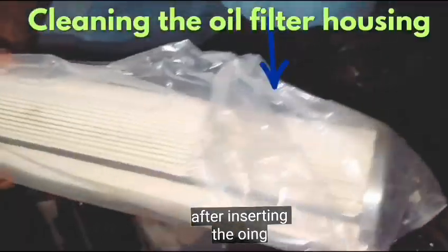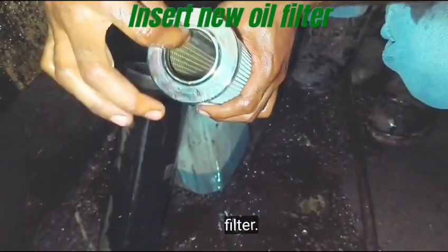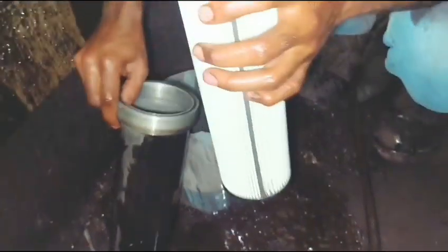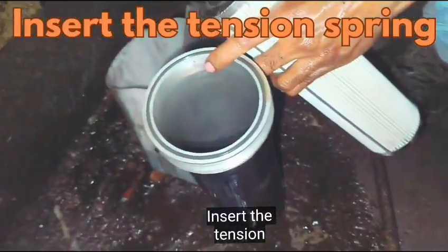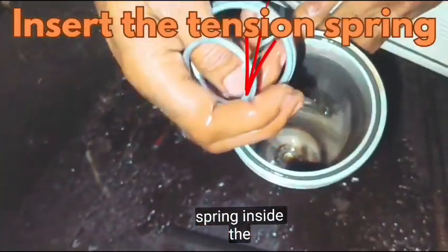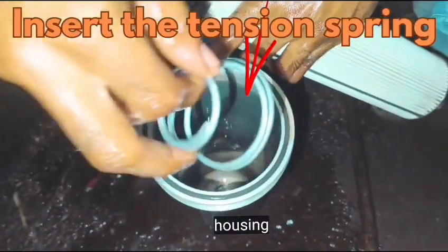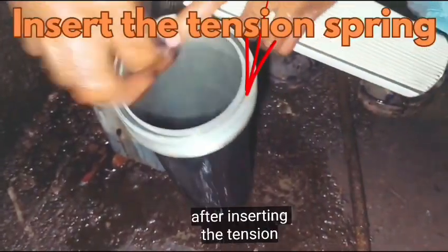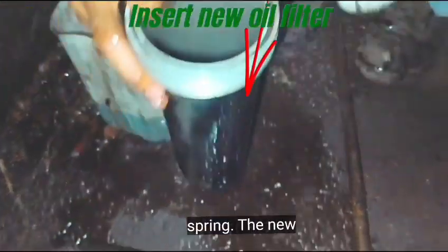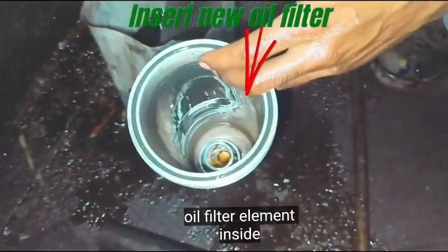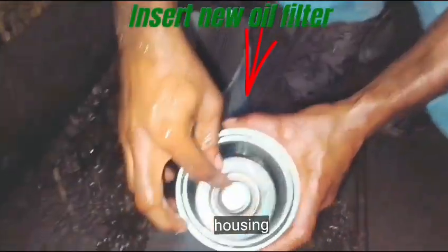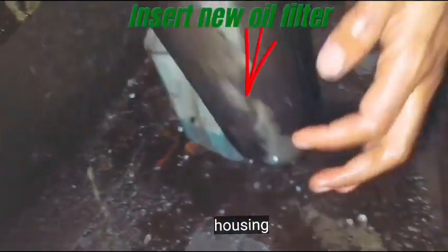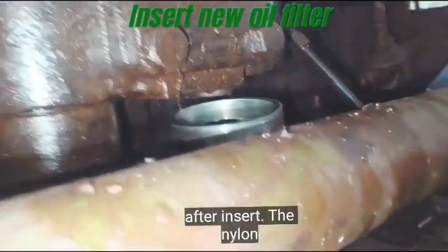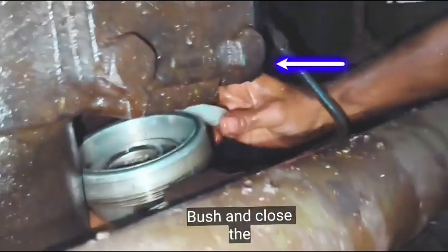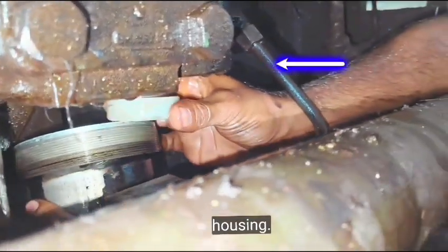After inserting the o-ring, take a new oil filter. Insert the tension spring inside the filter housing. After inserting the tension spring, insert the new oil filter element inside the filter housing. After that, insert the nylon bush and close the housing.